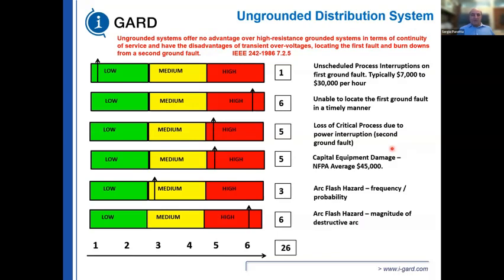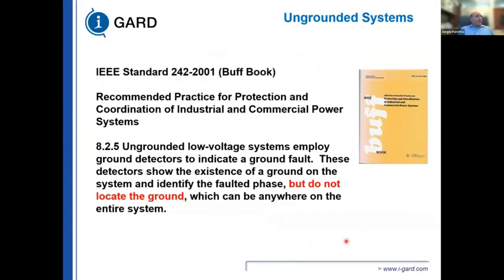So you can have 2 ground faults on the same system. Equipment damage is high. Arc flash frequency probability is medium, and the arc flash hazard for destructive arc current is high, because you can't find where the first fault is. You have phase to ground potentials that are phase to phase on the unfaulted phases, and you may have a second ground fault occur and an arc flash event. On the risk assessment meter, we have a number of 26.